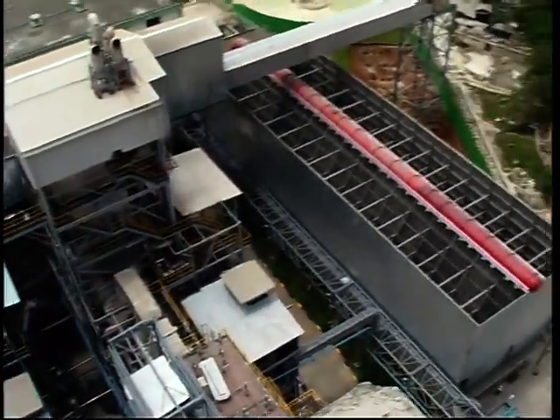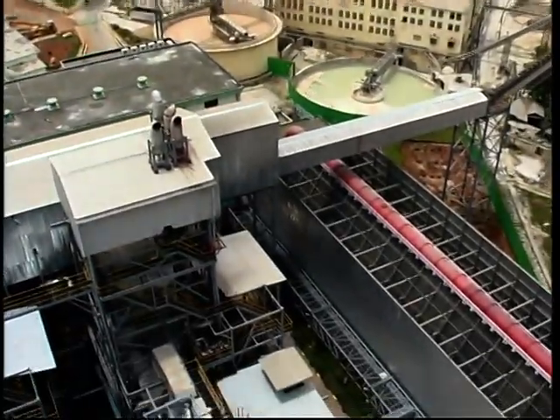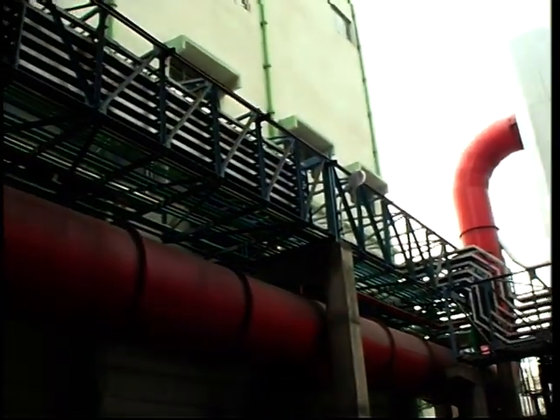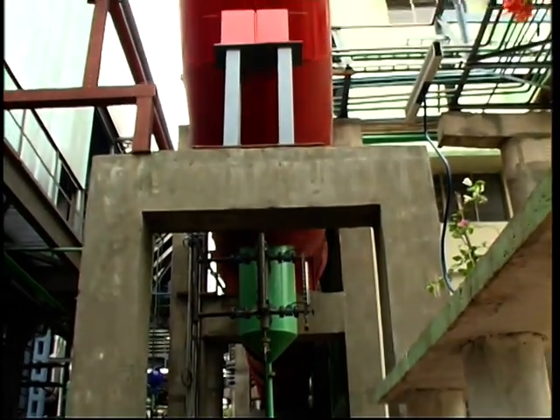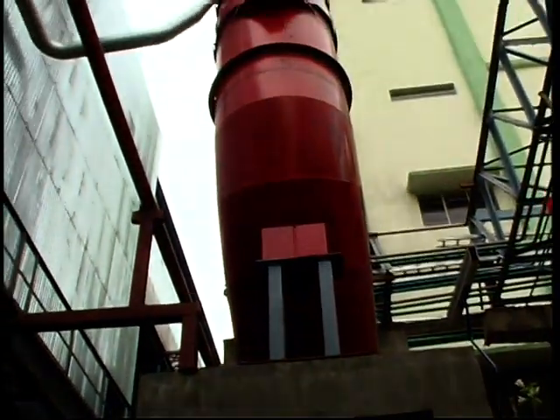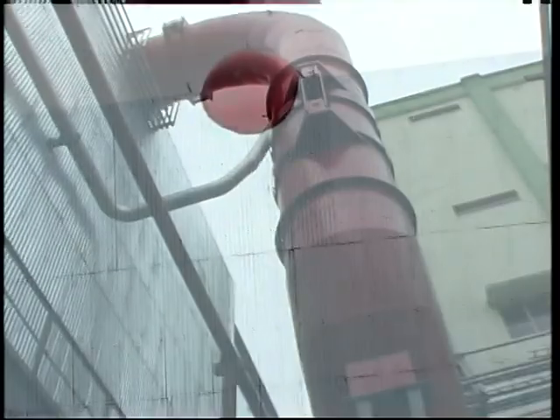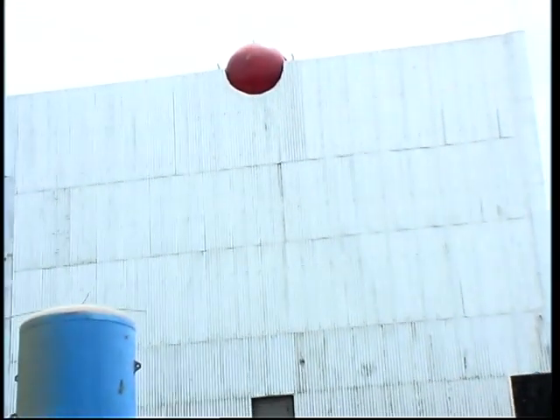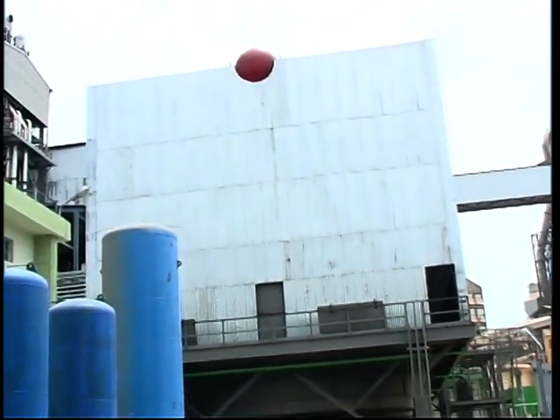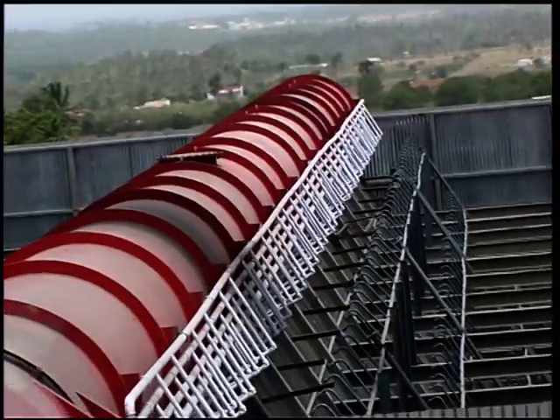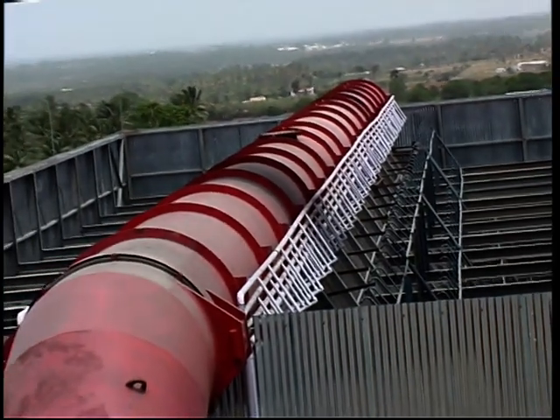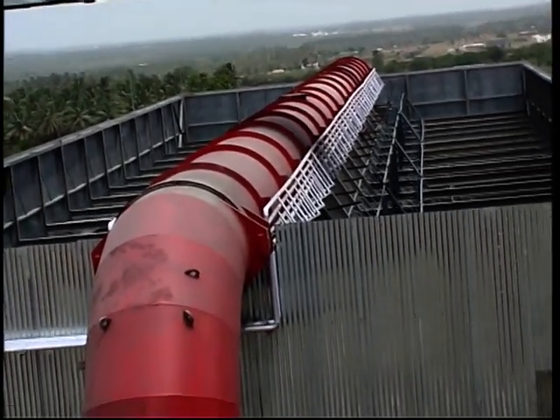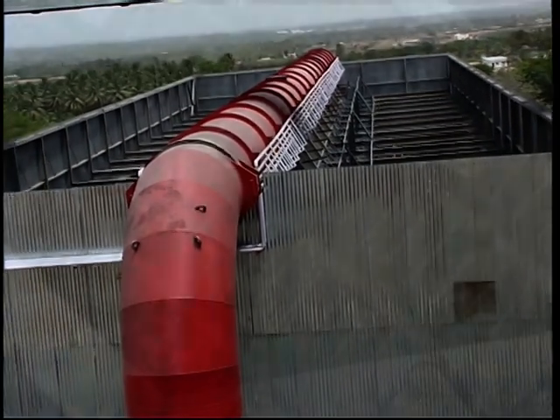Air-cooled steam condensers are not as expensive as might appear at first sight. While working out the economics, it has to be kept in mind that air-cooled steam condensers eliminate the entire recirculating water system associated with water-cooled condensers, such as cooling towers, circulating water pumps, circulating water pipes and valves, and so on. The higher fan power requirement of an air-cooled steam condenser is offset to a great extent by the saving in cooling tower fan power and circulating water pump power. Hence, whenever one is not sure of continuous availability of water of the desired quality, one should seriously consider the option of an air-cooled condenser.